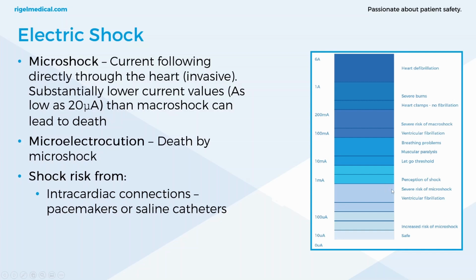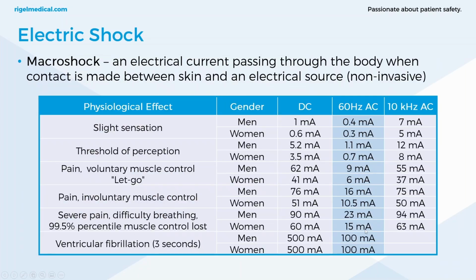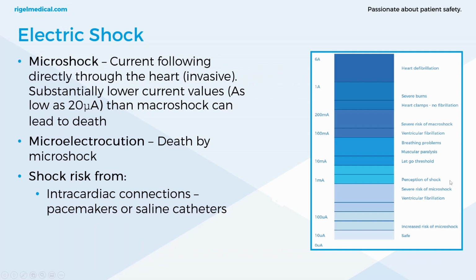We can see from the previous slide, ventricular fibrillation occurred at 100 milliamps, 50 to 60 hertz. Now this is for the commercial frequencies as well. It doesn't highlight that. It's much lower. An increased risk of microshock can occur as low as 20 microamps, where it can lead to death. So you're talking about a very low level of current, effectively 5,000 times less than that of macro shock. So there's a huge disparity there.